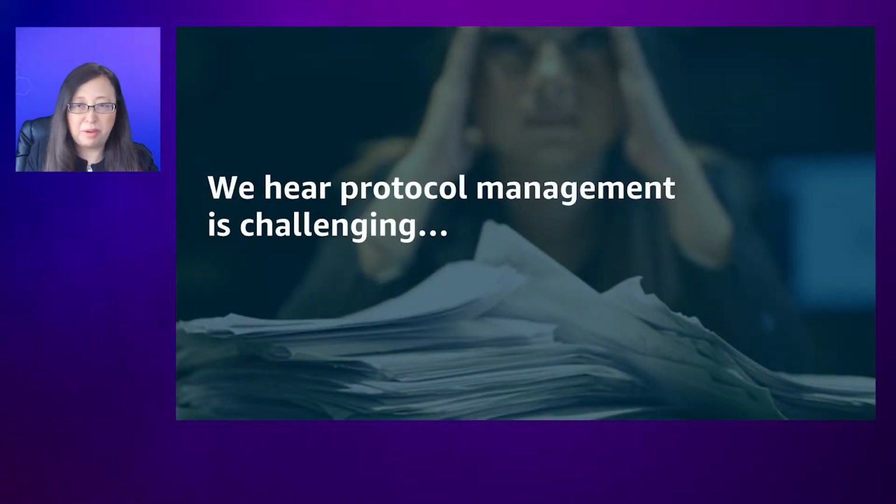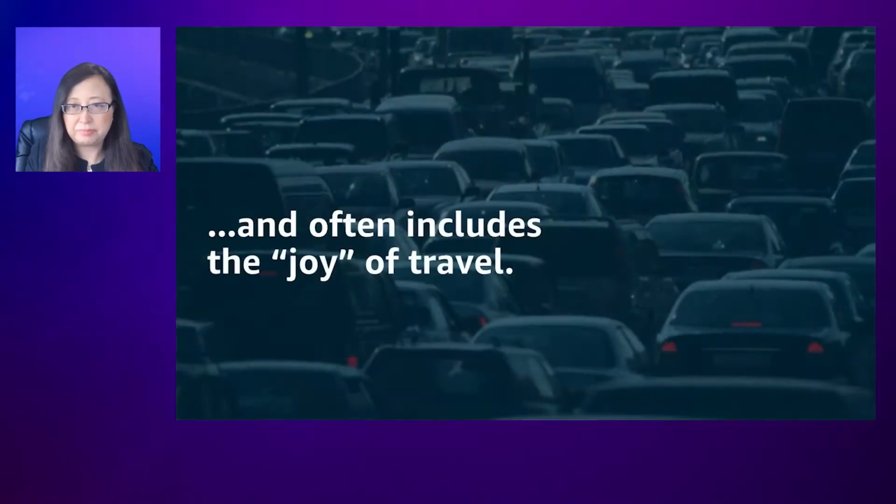But we hear from our customers, protocol management is super challenging. Among all the challenges, perhaps the biggest one is to get one set of standardized protocols everywhere. Today, our customers need to manually update each imaging device using a USB drive, driving to multiple sites, late nights, early mornings, weekends, a lot of less than ideal situations.